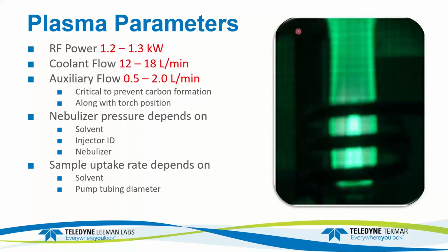I tend to go a little bit higher on the coolant flow than others might. I definitely want to prevent any problems with carboning of the torch, but I also want to prevent any issues with low flow torches that could cause them to melt. So I tend to run them a little bit higher than what others do. Auxiliary flow is to keep the plasma from causing carbon on the injector and on the intermediate or auxiliary tube. I tend to run this a little higher. I keep my torch higher in the coil than other people might, and I turn up the auxiliary flow to push the plasma away from the end.